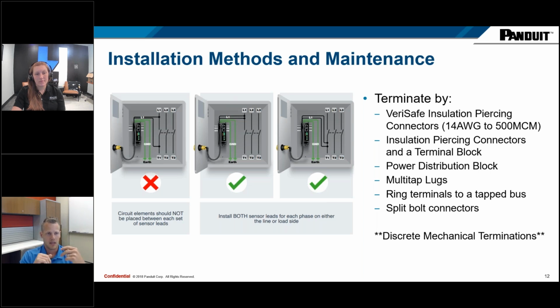Each pair of sensor leads for each phase should not span a disconnect or a device. They should be on the same side, line or load, not line and load. You don't want them to span the disconnect. But that's pretty much it. 2 mechanical separate discrete terminations, and then that can allow it to go and do its connectivity verification.